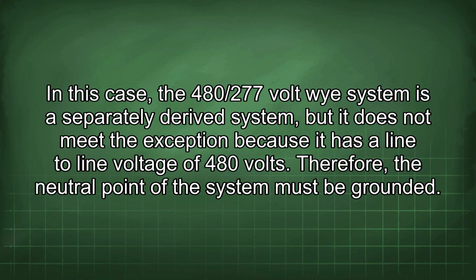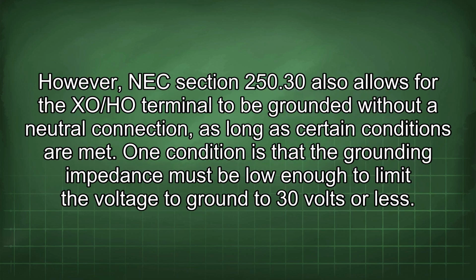In this case, the 480/277 volt Y system is a separately derived system, but it does not meet the exception because it has a line-to-line voltage of 480 volts. Therefore, the neutral point of the system must be grounded. However, NEC Section 250.30 also allows for the XO/HO terminal to be grounded without a neutral connection as long as certain conditions are met. One condition is that the grounding impedance must be low enough to limit the voltage to ground to 30 volts or less.